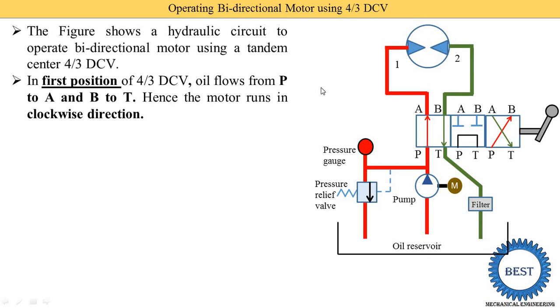During the first position, port P is connected with port A, and port B is connected with port T — oil flows P to A and B to T, hence the motor runs in a clockwise direction. Pressurized oil from the pump enters port P, passes P to A, and enters the left side of the motor. We draw this in red color for high pressure. The oil strikes the vanes of the motor and the motor rotates clockwise. Oil exits from the second side, comes into port B, flows B to T, and goes to the oil reservoir through the filter. This is the first position.